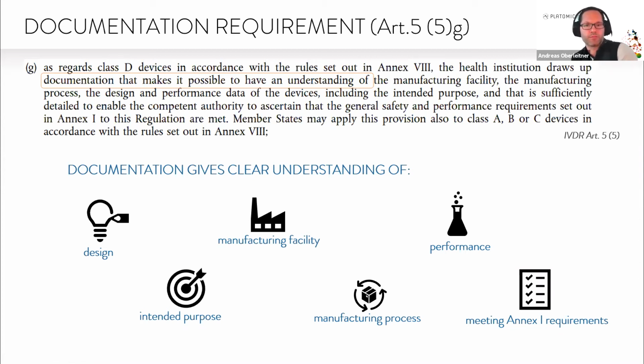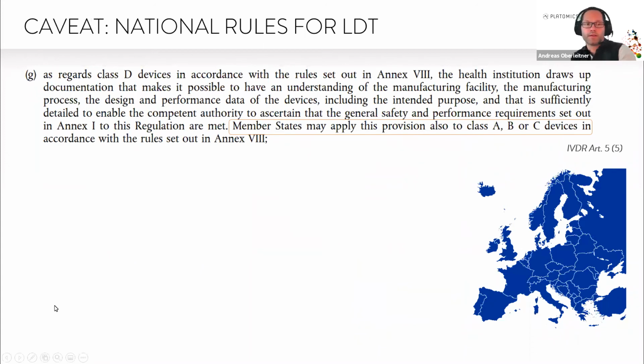requirements. So moreover, it also implies that the healthcare facility must classify their LDT or developed device according to the IVDR, because some requirements relate to the class of the device. Genetic tests for human diagnostic purposes, by the way, usually fall within IVDR Class C. So now, of course, one could think that the just considered paragraph 5.5G only concerns Class D devices and is therefore not applicable to a genetic test as a Class C device.